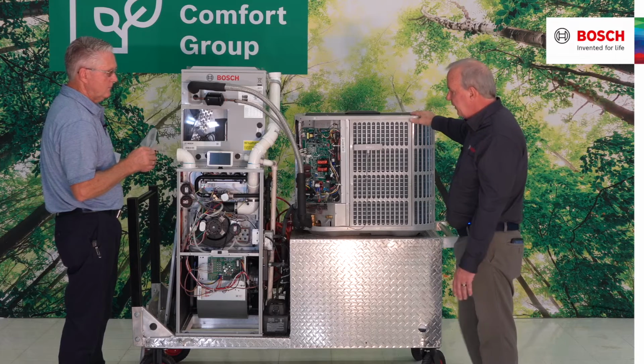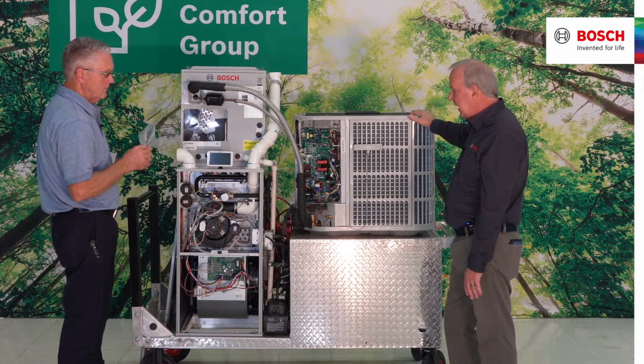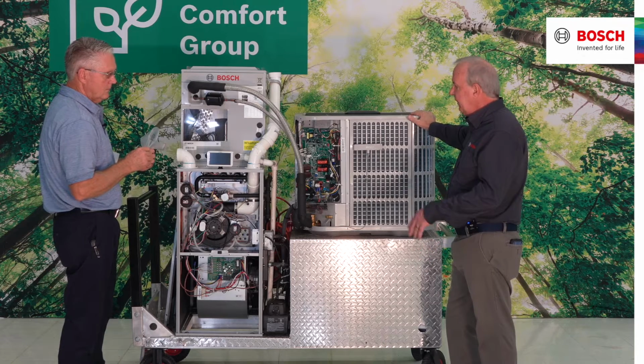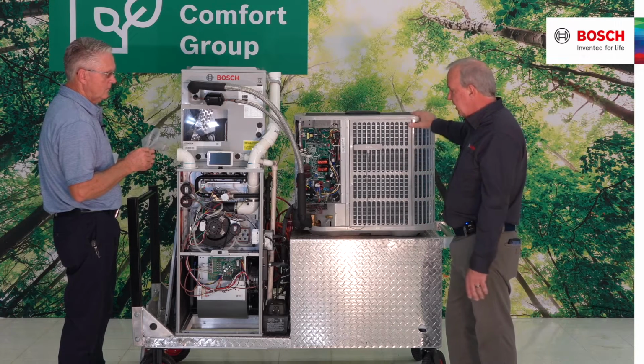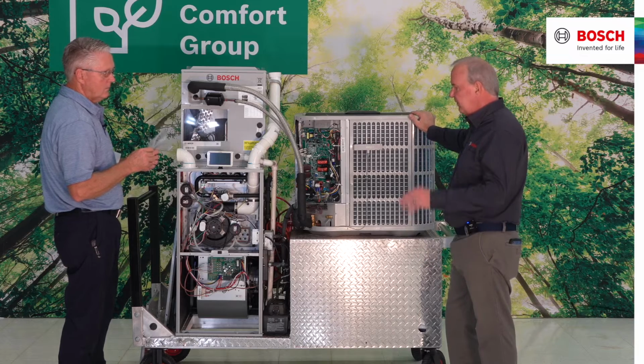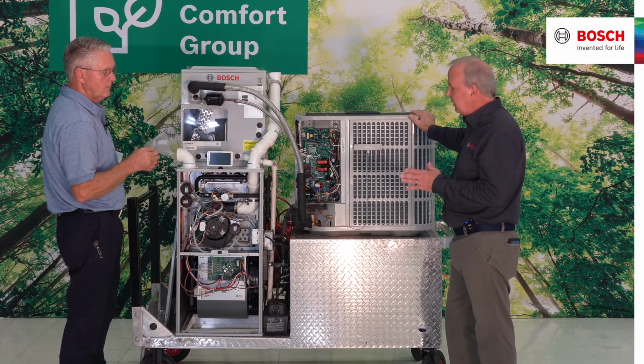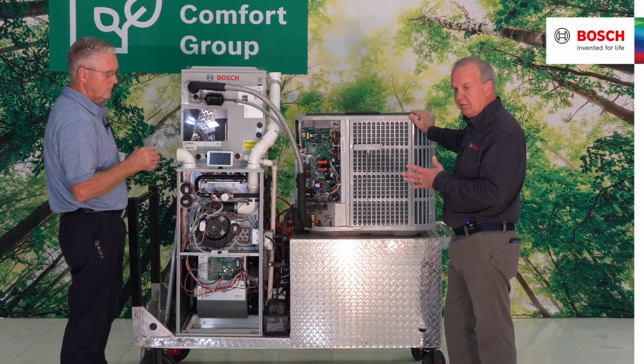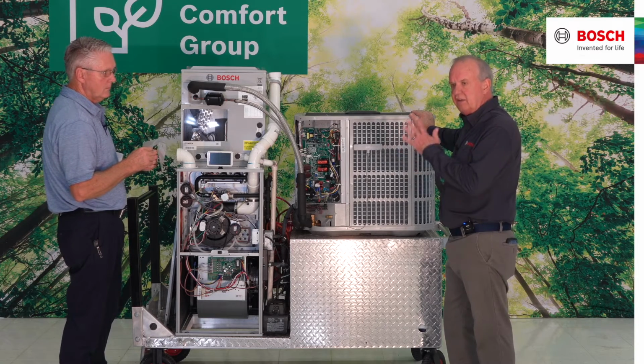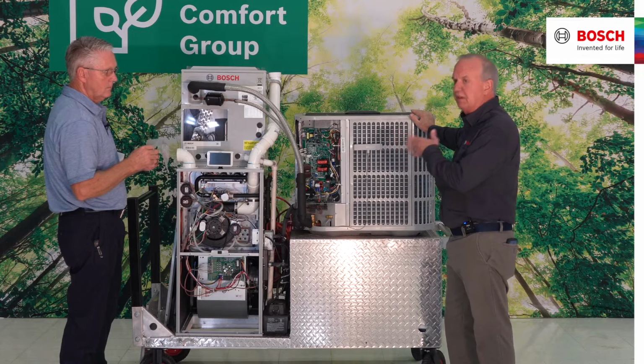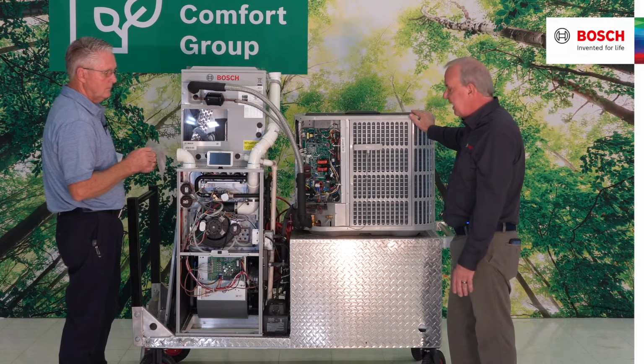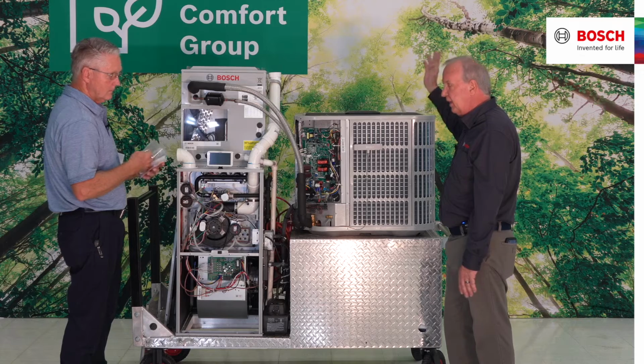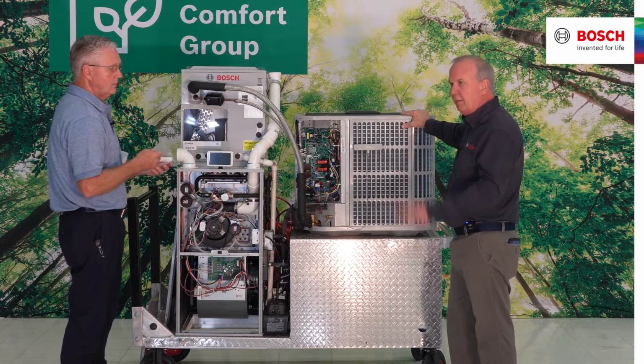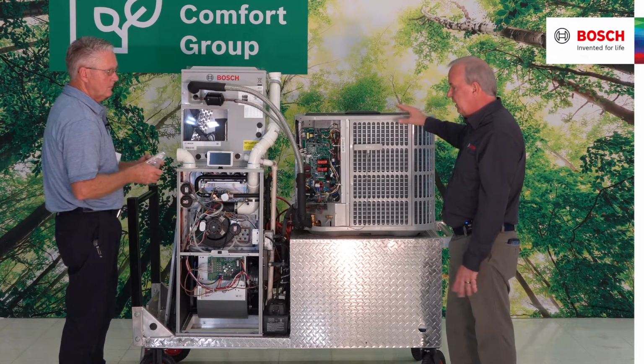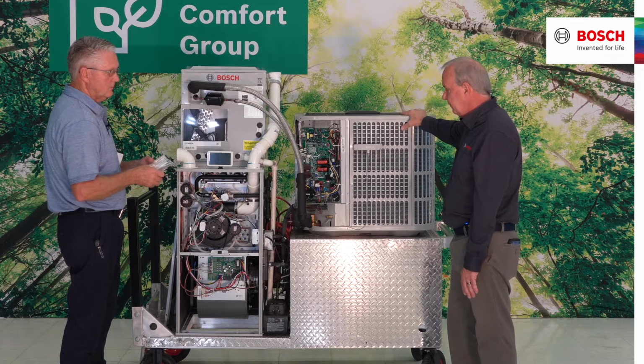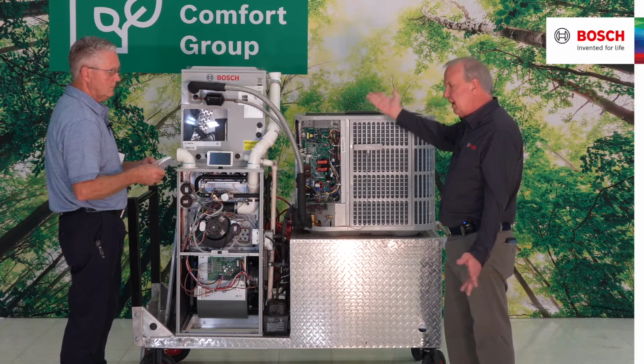Yes, there is. So the furnace, straight out of the box, is good for 2,000 feet above sea level and under. If there is a need for higher altitude applications, there is a chart that we follow. A different orifice needs to be installed for 2,000 to 4,000 feet above sea level, 4 to 6, 6 to 8, and all the way up to 10,000. We actually have some furnaces in higher elevations in Colorado, and even in Arizona, that are running the different orifices. And they may be LP furnaces or they may be gas furnaces.